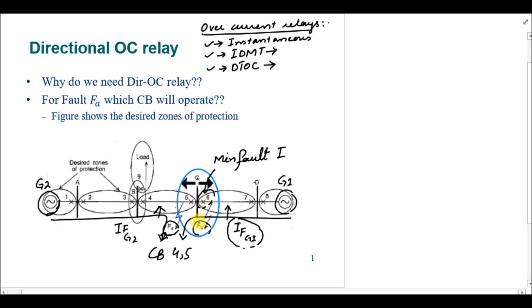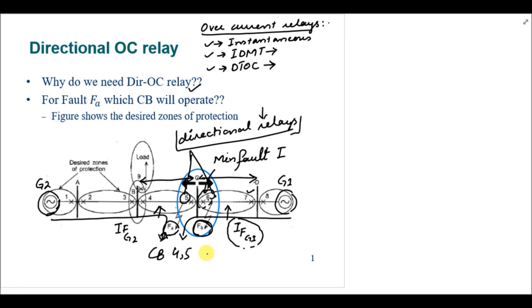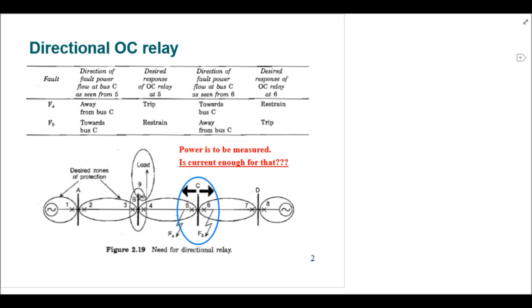To avoid this, we have to use directional overcurrent relays so we can ensure that the fault is occurring in line BC and not in line CD. Similarly, for fault FB, circuit breakers six and seven should operate but five should not. Therefore, relays at circuit breakers five and six should be directional relays, or overcurrent relays with a directional element attached, to distinguish between faults within the zone and outside of it.